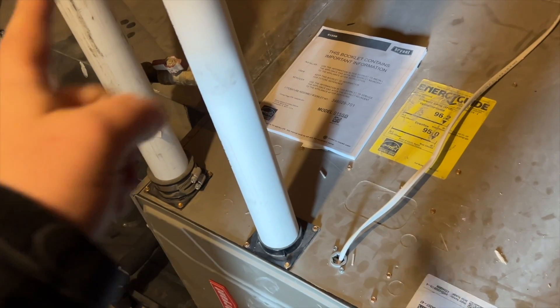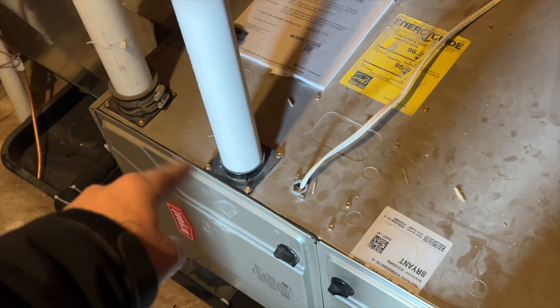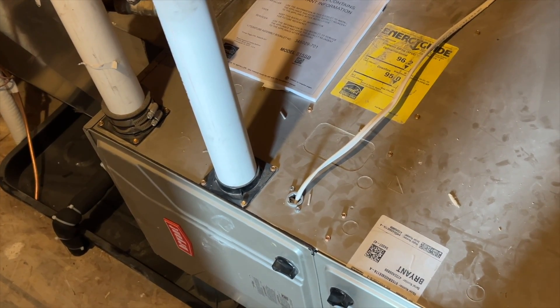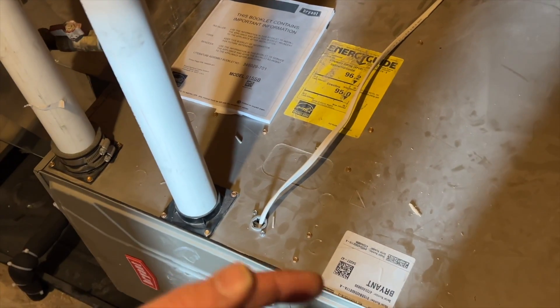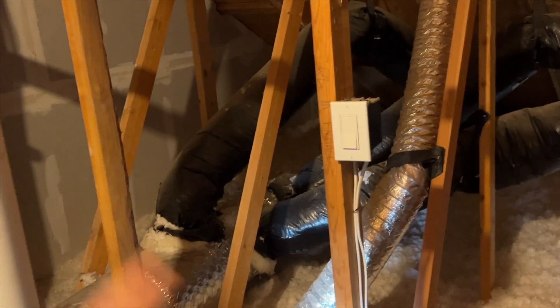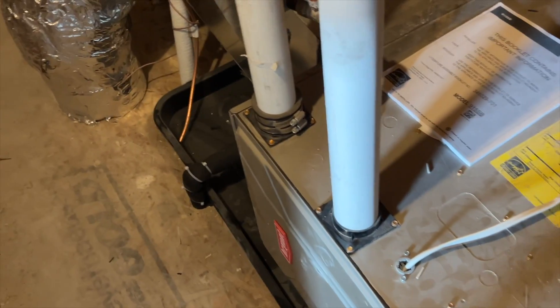We're in an attic space and there's a little bit of insulation but nothing on the roof. This is a condensing furnace — what do you think is going to happen when it gets below freezing in here? All the collector boxes are going to freeze up and then the heat's going to go down. I've come across this multiple times where they install a unit in an attic and it's not insulated. If you're going to put one in an attic and not insulate the space, use an 80% unit, not a 90%.